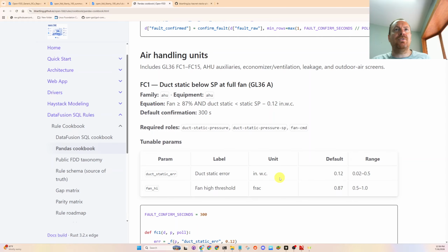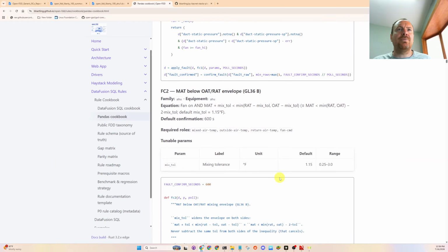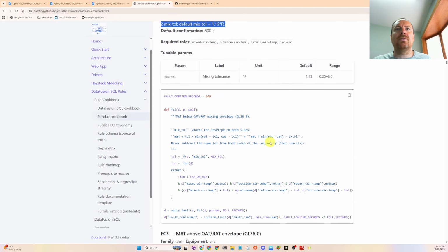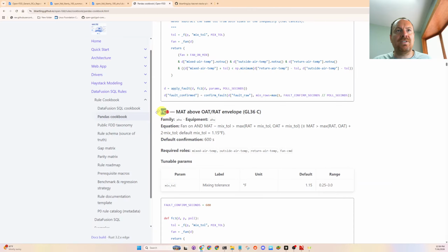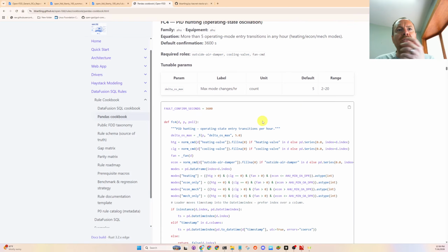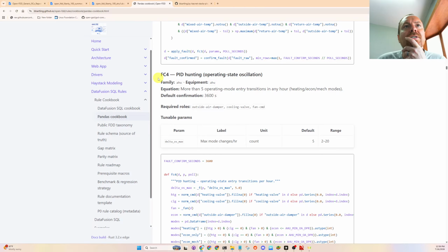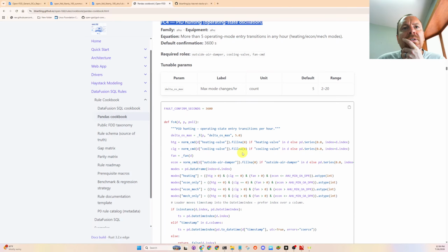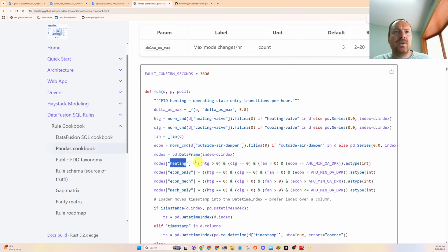Okay, so we have lots of air handling unit stuff. So this is getting updated nicely. I just wanted to prove that these docs are continuously getting updated with the equations. Anything with the FC is a Guideline 36 equation. This is actually the PID hunting for the entire air handling unit system, where the air handling unit is oscillating in and out of heating, economizing only, economizing plus mechanical, and mechanical cooling mode, all based off of valve positions.